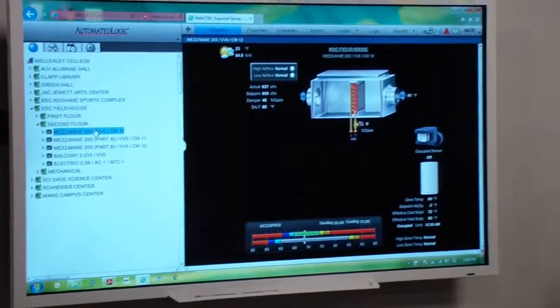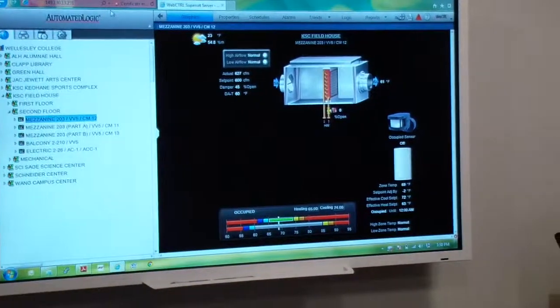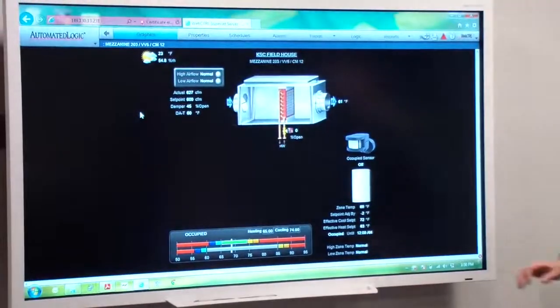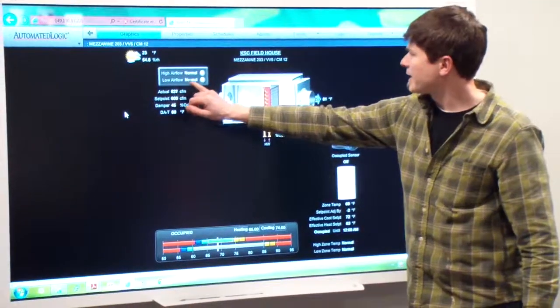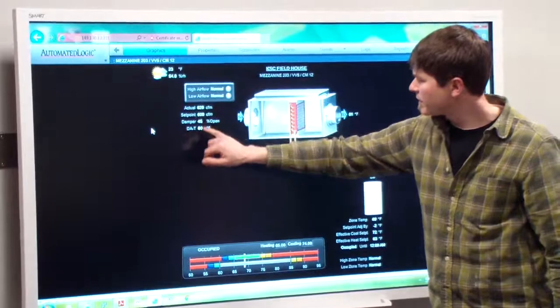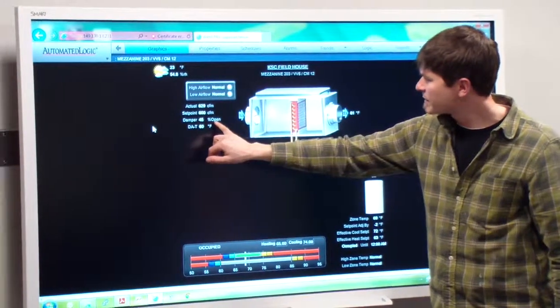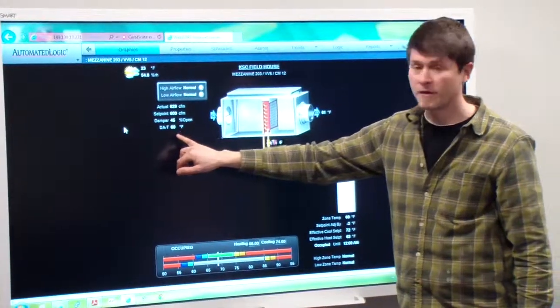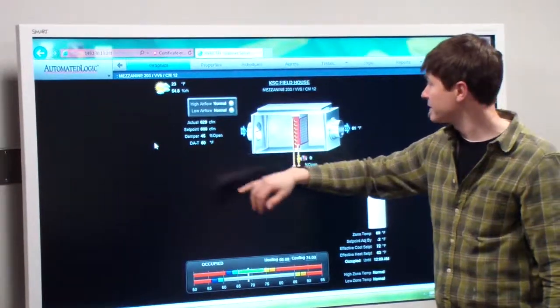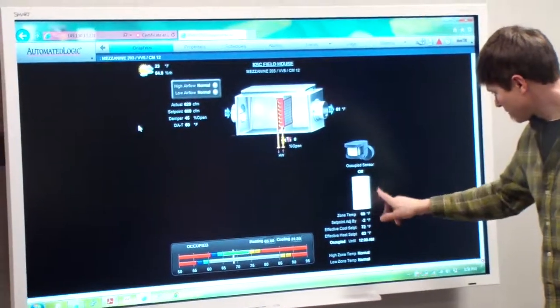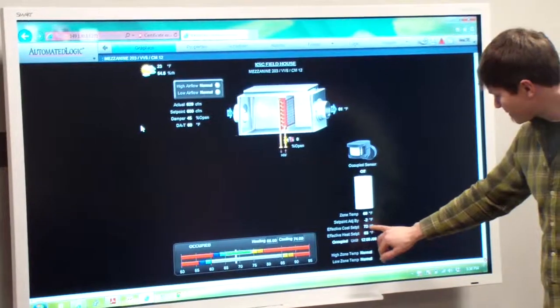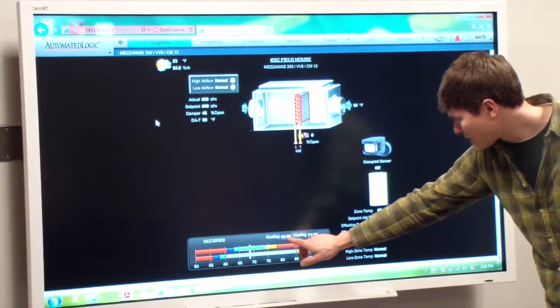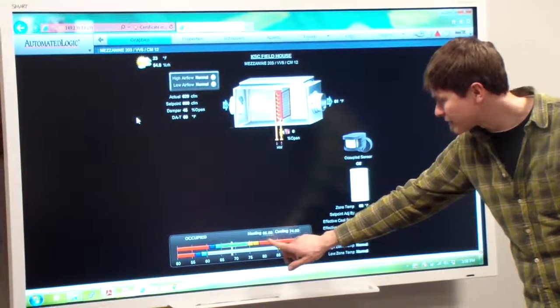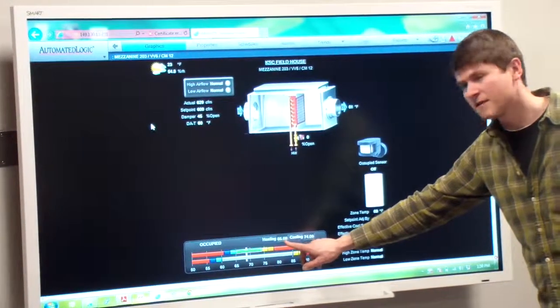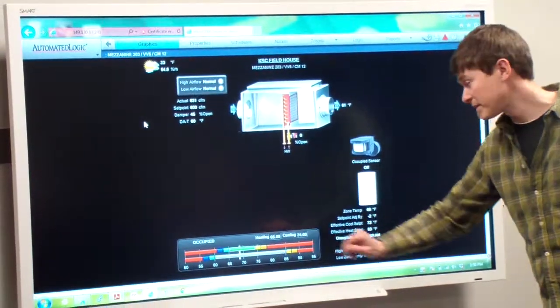Here are the mezzanines. You can see the same thing with your high airflow, low airflow, which come through these blocks. Your damper is at 45% open. Discharge air temp from AHU10 is 60 degrees. Thermostat, reading for your temperature, is what we had changed earlier to try to make them a little more comfortable upstairs. It's now a 65-degree heating set point.